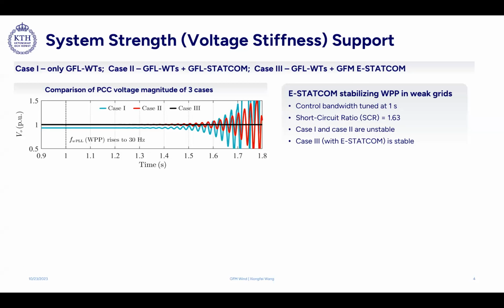Here we perform 3 case studies. Case 1 is only grid following wind turbines in the wind power plant. The second case is grid following wind turbines with the conventional grid following STATCOM. And the third case is with the grid forming E-STATCOM. In those 3 cases, we try to push the SCR to a much lower value to represent a weak grid condition.